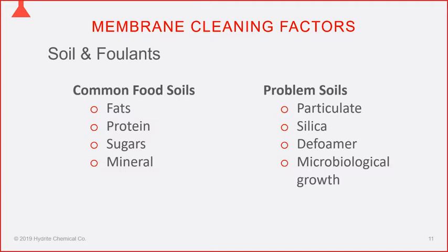Defoamers are problematic not only for their silica content but also because many are made of insoluble substances like modified vegetable oils or other materials that are very difficult to remove from membranes — requiring aggressive cleaning practices with lots of surfactant and solvents. Microbiological growth is controlled by routine sanitizing. Skipping sanitizing can be very dangerous: microbes can get onto the permeate side of the membrane, which is the low-pressure, low-flow side, and once there it's nearly impossible to get them out.